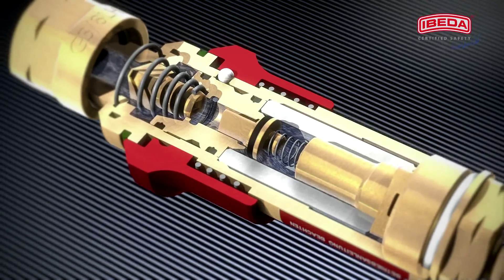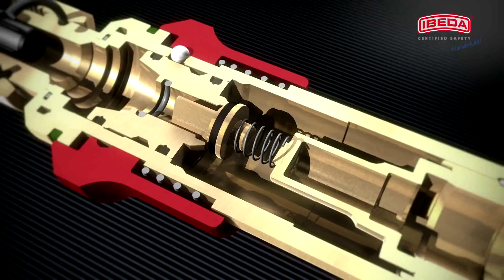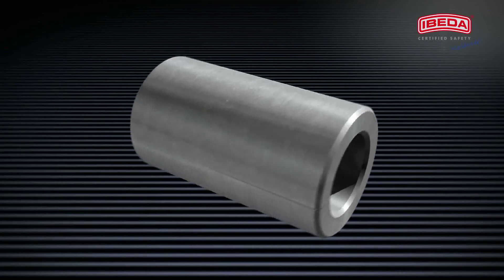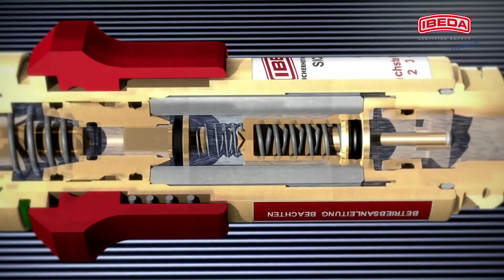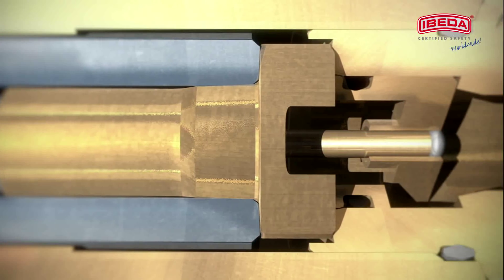A gas non-return valve or check valve alone, however, cannot stop a flashback. The flame would pass through the device, causing irreparable damage to the gas non-return valve. The flame arrester of the IBEDA safety devices stops a flashback while reliably protecting the gas non-return valve. This process is executed in perfect sync with the integrated flame deflector.